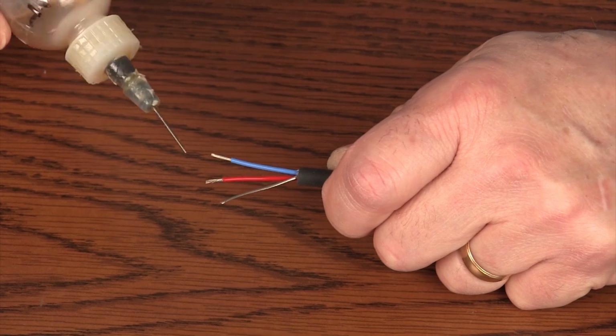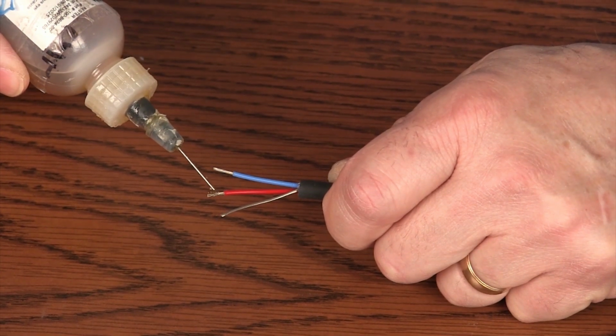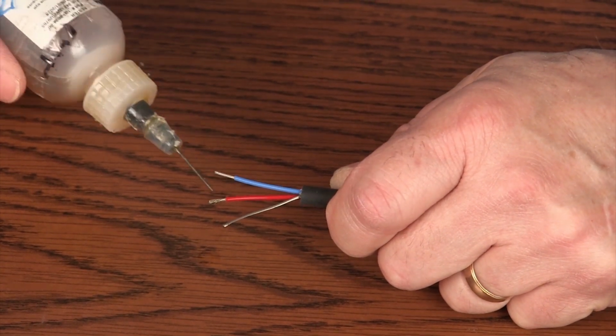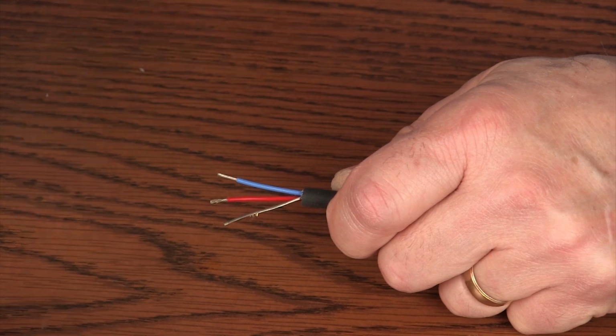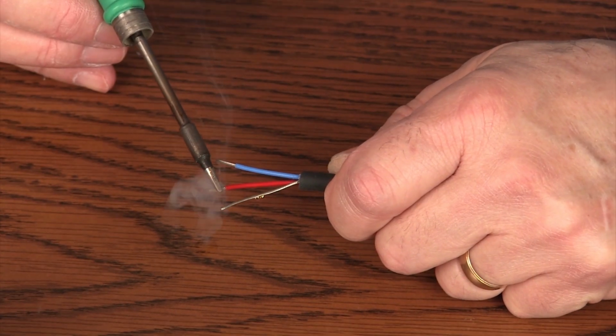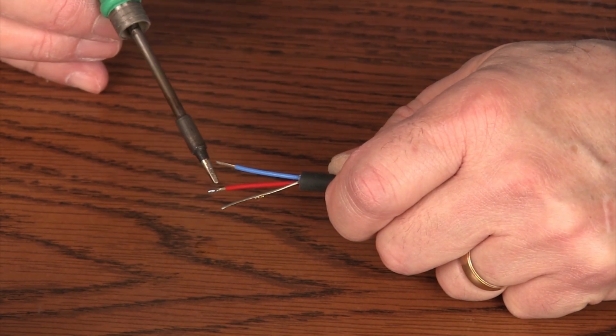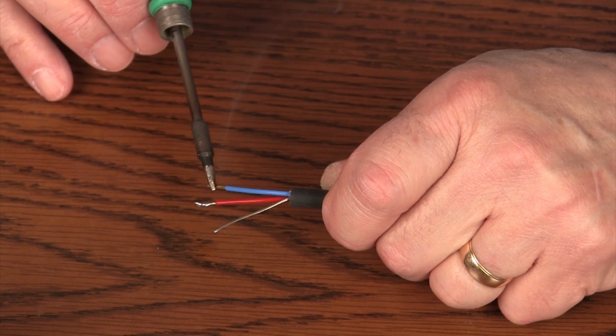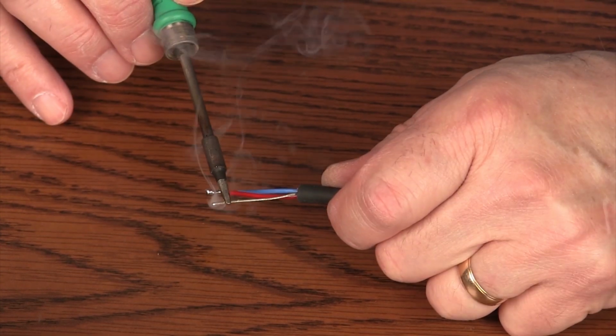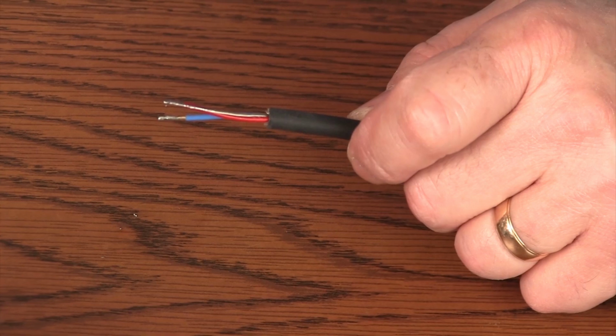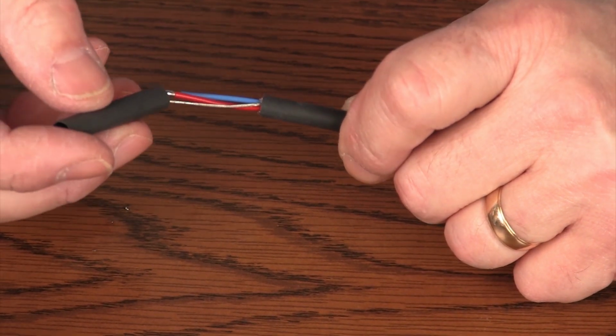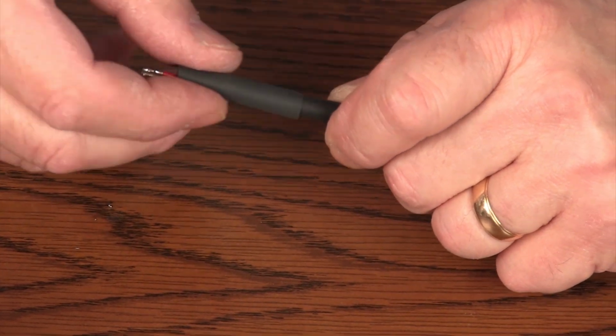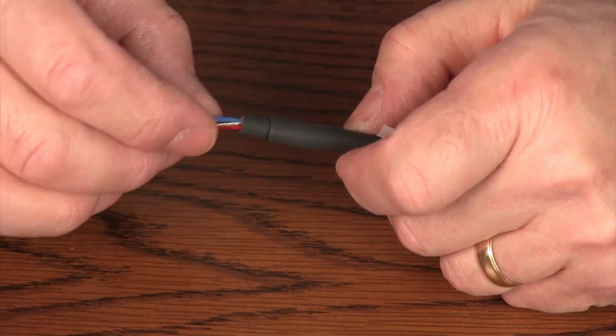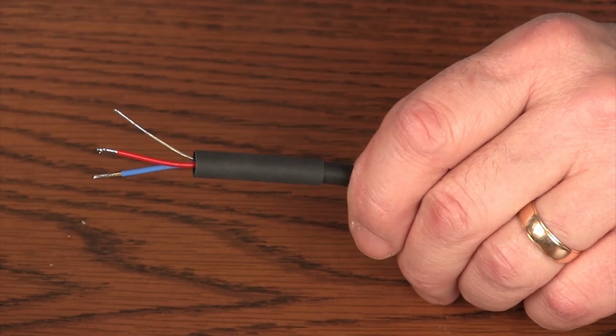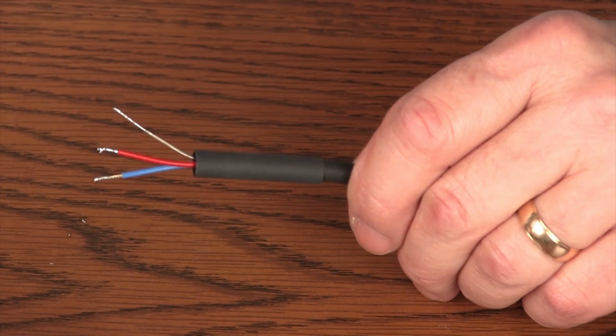An optional step is to tin the leads. This makes them easier to install in the termination box. All of our cables are available to be ordered with stripped, tinned, and labeled leads. As part of that service, IMI will also install heat shrink at the point where the conductors exit the cable jacket and shield for added strain relief and protection.